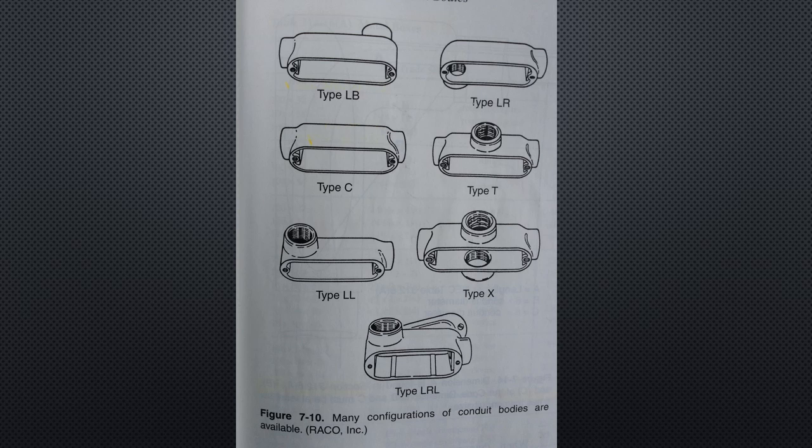Boxes and conduit bodies must be large enough to provide adequate free space for the conductors entering and exiting. If the enclosure is too small, the ambient temperature around the conductors becomes too hot. This weakens insulation and increases resistance. Carefully read section 314.16 C2 to determine if a splice or tap is allowed in a conduit body. Section 314.5 specifically forbids splices, taps, or devices in short radius conduit bodies, capped elbows, and service entrance elbows.